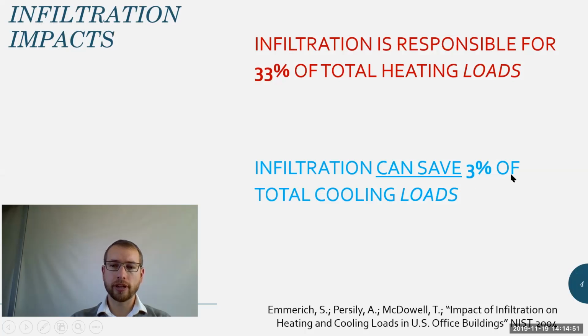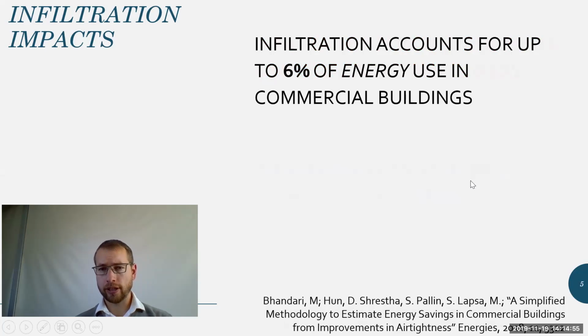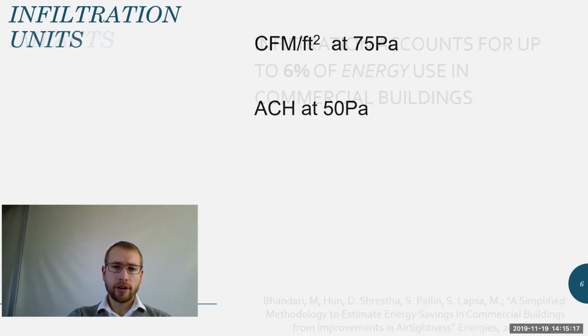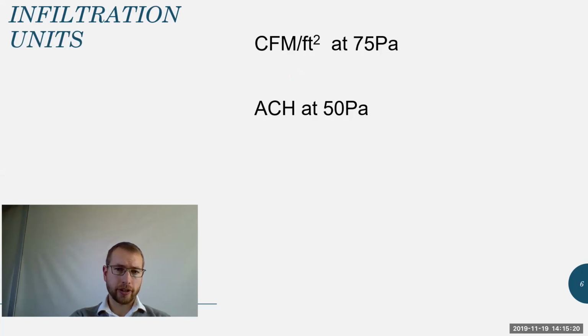These numbers are based on a nationwide study of commercial office buildings. But those are the HVAC loads, not necessarily the energy use in the building. If you're looking more holistically at the total energy use in a building, infiltration accounts for up to 6%. Now, that's still a pretty big number. If we can reduce that, then we can definitely see some savings from just a purely financial perspective. All right, so how do we actually measure it in terms of units? There are two main ways. There are a couple others, but I'll just focus on two.